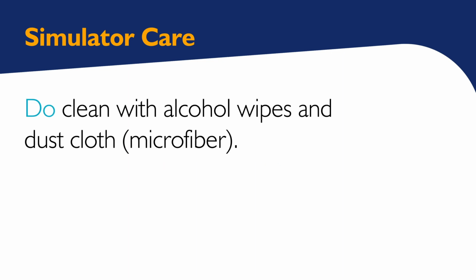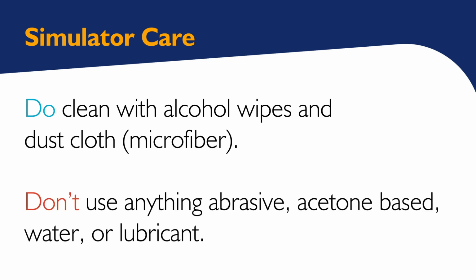During travel and from prior use, the machine may need some general care in appearance. When caring for the simulator, it is important to know the do's and don'ts of simulator care. In general, you should only use alcohol wipes and a dust cloth or a microfiber to clean the monitor, tools, and base. Never use anything abrasive, acetone-based, water, or lubricant on the UroLift SIM.